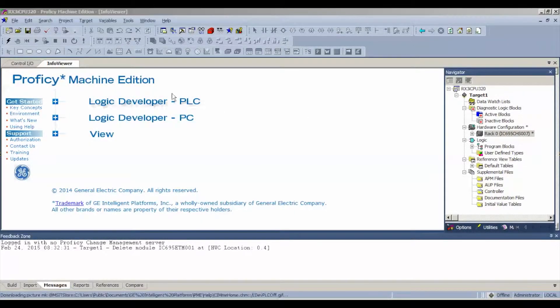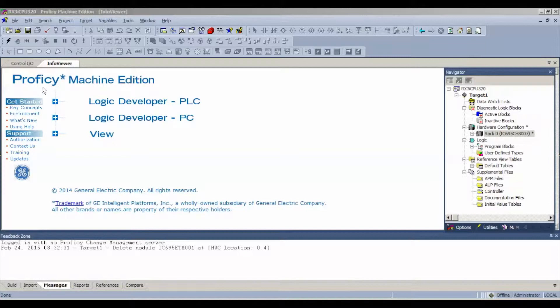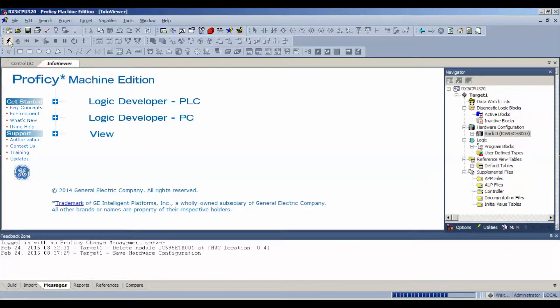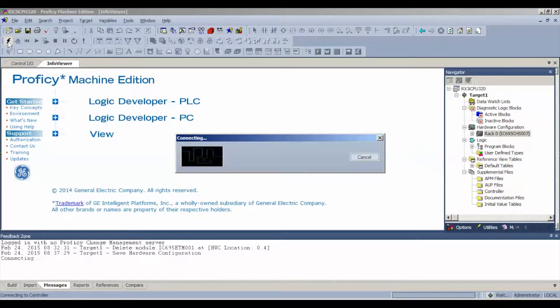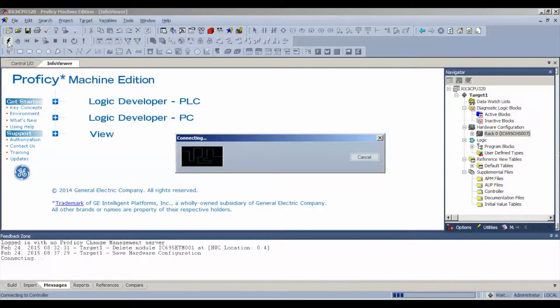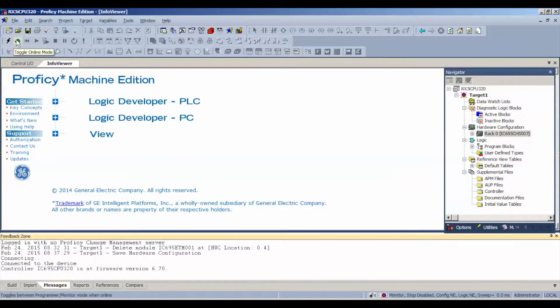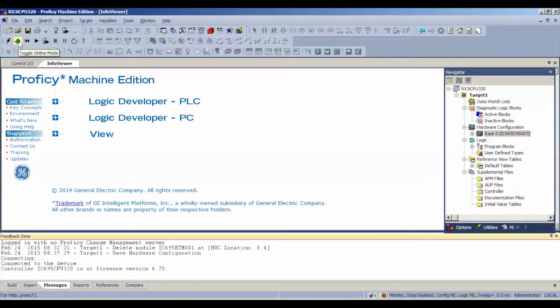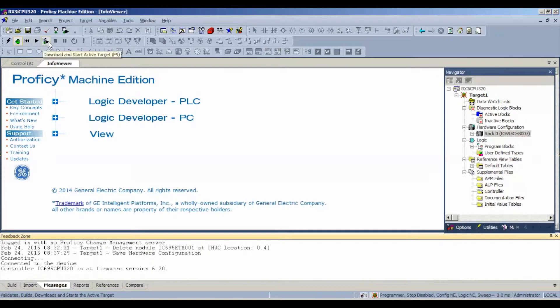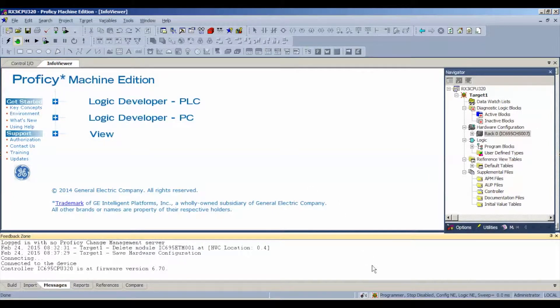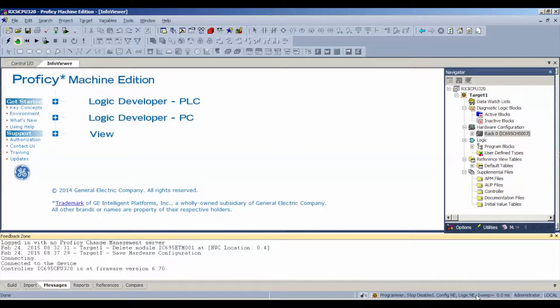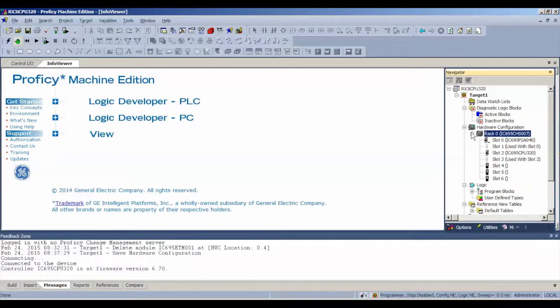The first thing that I want to do is connect up to the processor by hitting the lightning bolt icon and then the green handprint icon which is the toggle into online mode. You can see that all these open up and highlight. If you look down below, if you follow my arrow, you can see that the mode that we're in right now or the status is programmer mode, stop, disabled, configuration and logic are not equal. That's because this processor was doing something different than what we're asking it to do today, the last time it was being used.